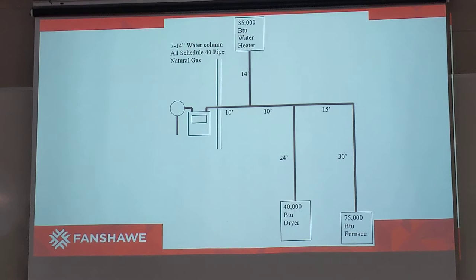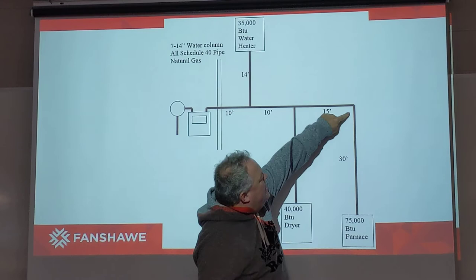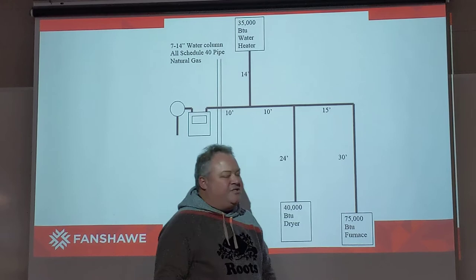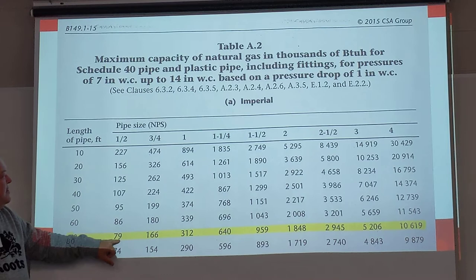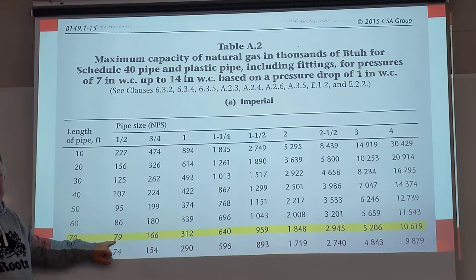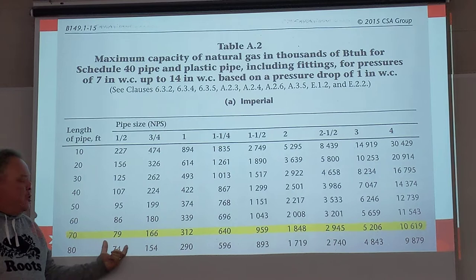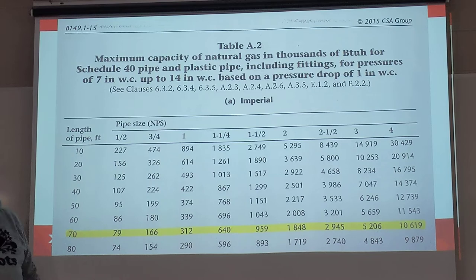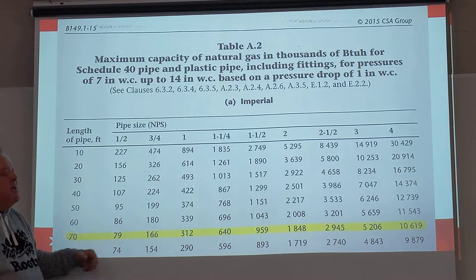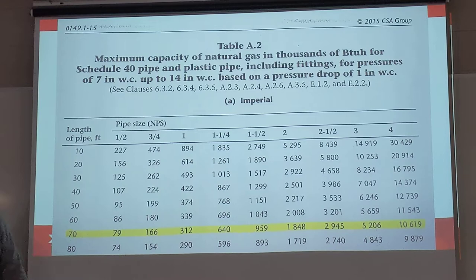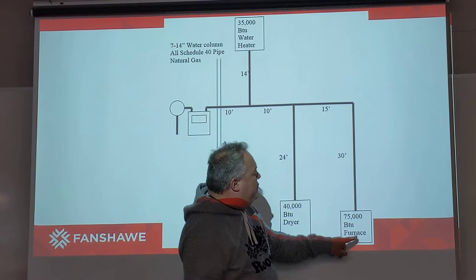We're looking at a 75,000 BTU appliance. This 30-footer and this 15-footer both serve the 75,000 BTU furnace. How big does that pipe need to be? At the 70-foot application, because we only have 75,000 BTUs, we're able to utilize a half-inch pipe with a capacity of 79,000 BTUs. Note that these tables do not show the three zeros — it's assumed we know there are three zeros behind each capacity value. If the furnace had an input of 85,000 BTUs, we'd have to step up to three-quarter inch. Because we only have 75,000, we can use a half-inch line. So both the 15-footer and the 30-footer coming down to the furnace are going to be half-inch.